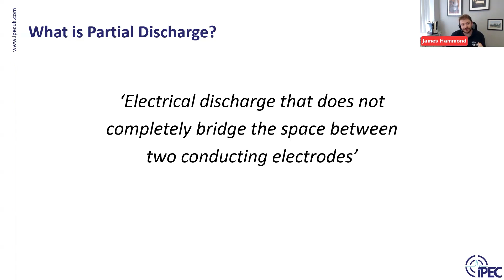So just to get everyone on the same page, I'm just going to quickly go over what partial discharge actually is. This here is the dictionary definition: an electrical discharge that does not completely bridge the space between two conducting electrodes. It's essentially a small spark. That's how I think of it anyway. A small spark that is constantly damaging, corroding, breaking down insulation if there is any type of defect.